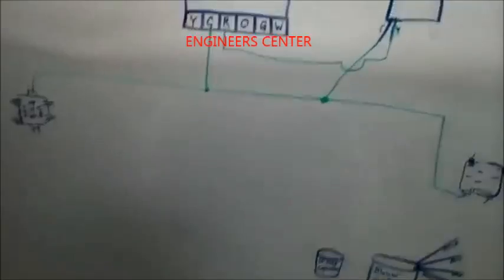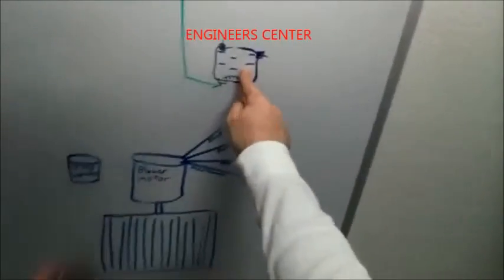Transformer, common, send common everywhere. Everything that needs common, just give it to it. That thing needs common, it needs 24. Your contactor needs 24 volts to close, so we're going to give it 24, or half of 24.